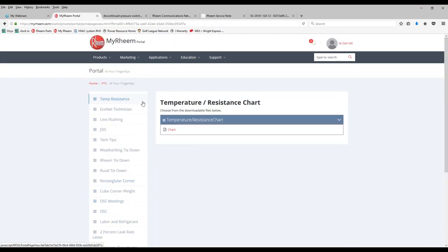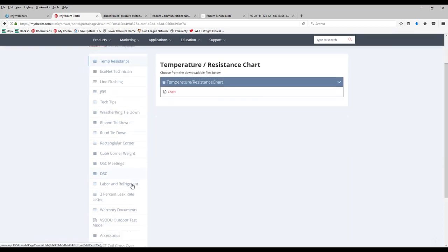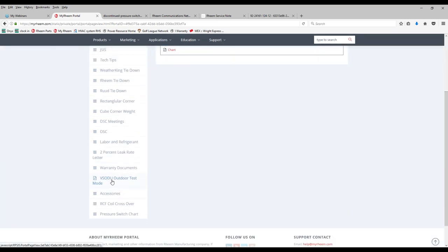The very first thing is the temperature rise or temperature resistance chart. If you click on the chart here, it'll give you the 10K ohm temperature resistance chart that they use for their heat pumps and their sensors. If you scroll down through, you'll see some other things like a variable speed outdoor unit test mode, how to put it in a test mode, some accessories, your pressure switch charts.